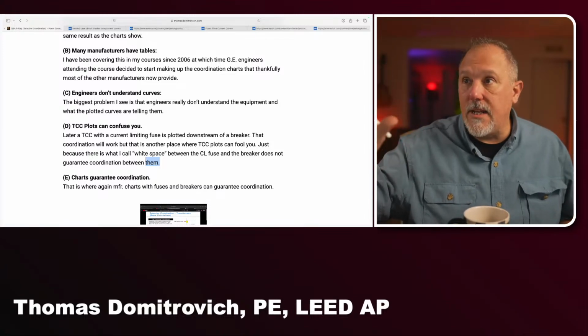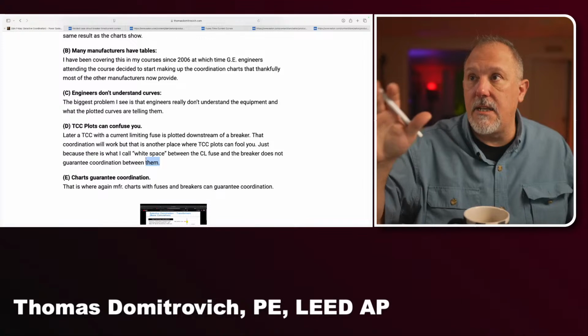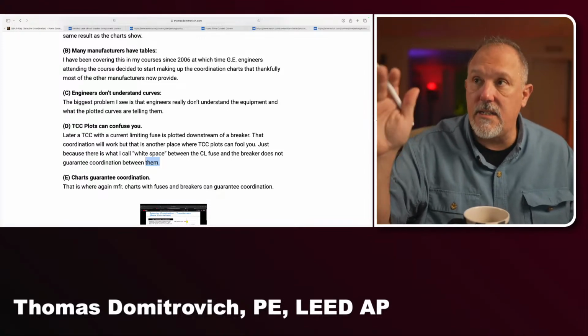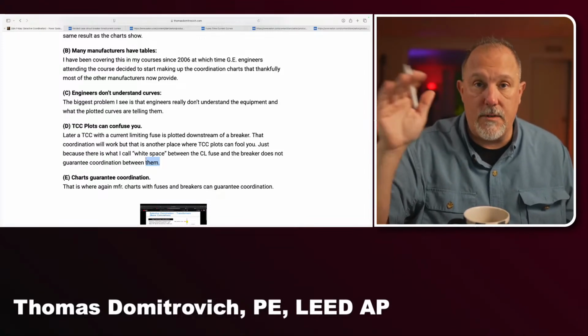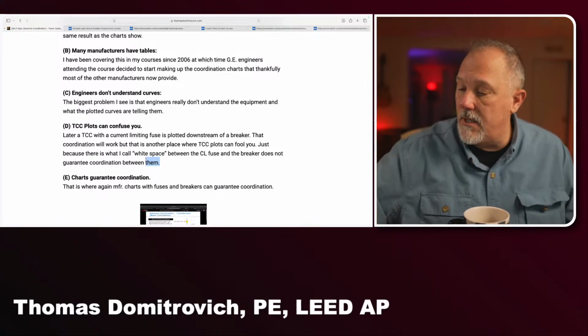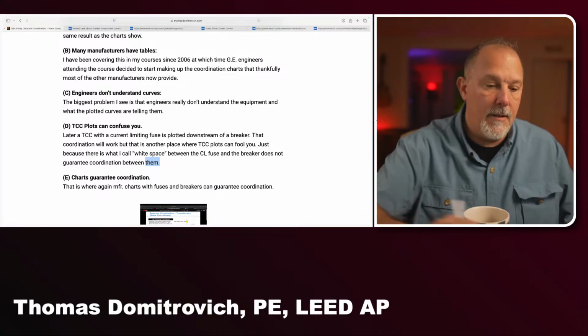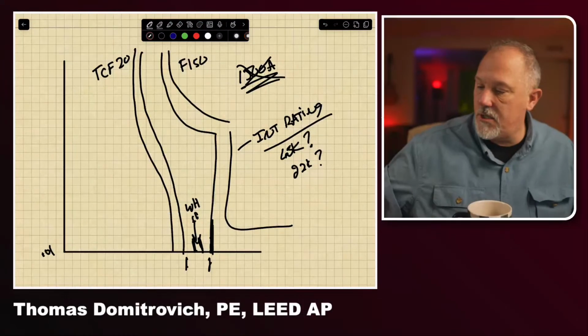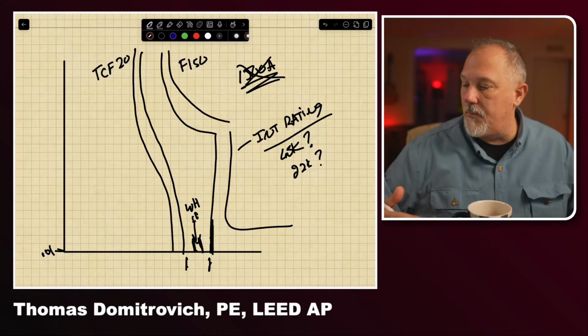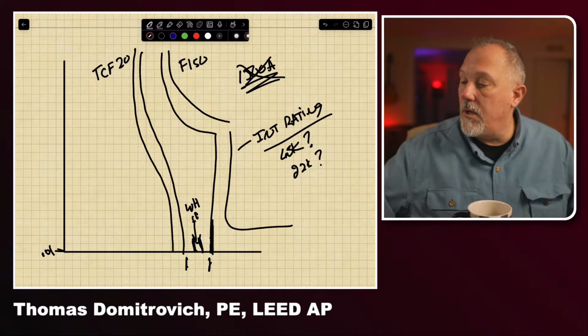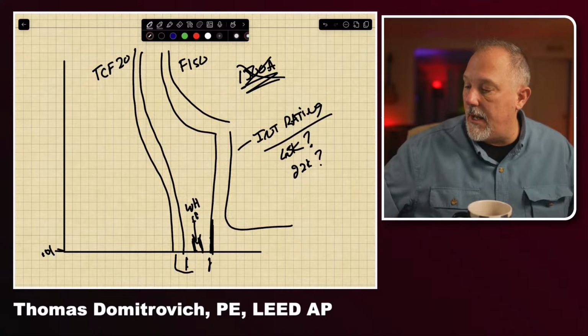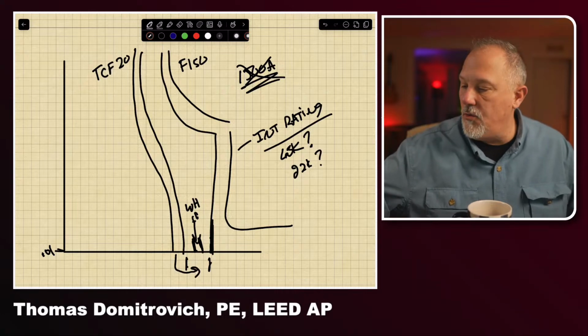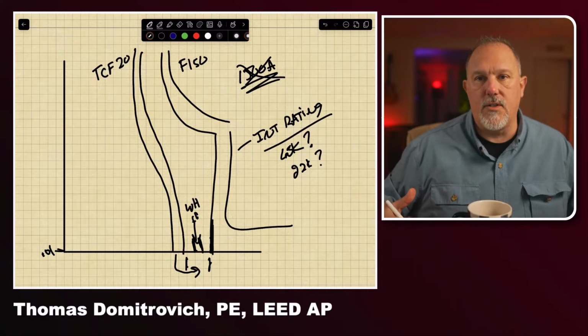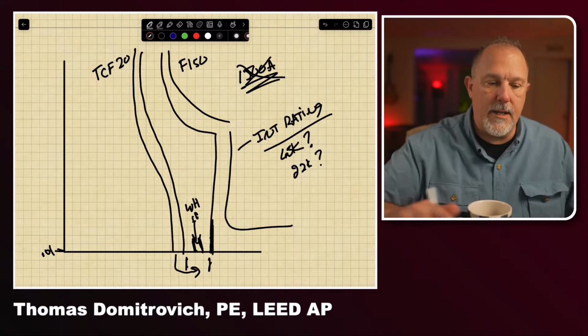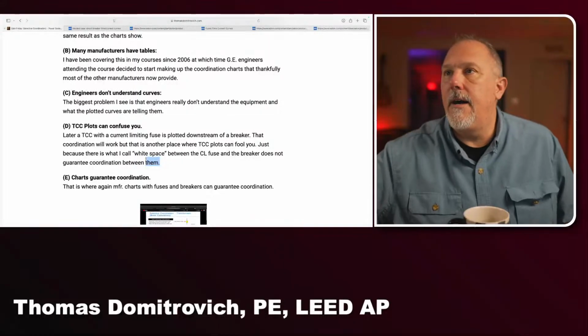All right, so that's what he was commenting on in the TCC, and I called that TCC plots can confuse you, and I agree. Nihad pointed out the 0.01 second issue is one of those issues. That 0.01 second, cutting it off at 0.01 seconds, only looking at what's on the screen, and the fact that with any of those breakers, you don't see what's going on below 0.01 seconds. And we have to go to the tables. That is definitely an issue.